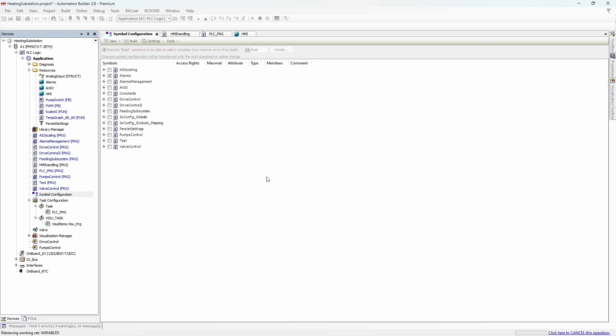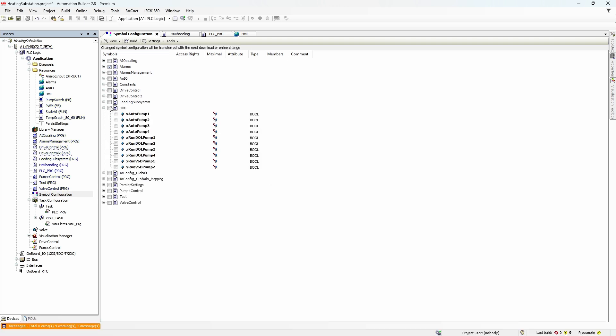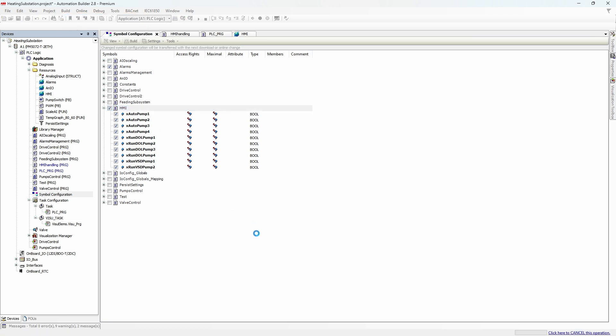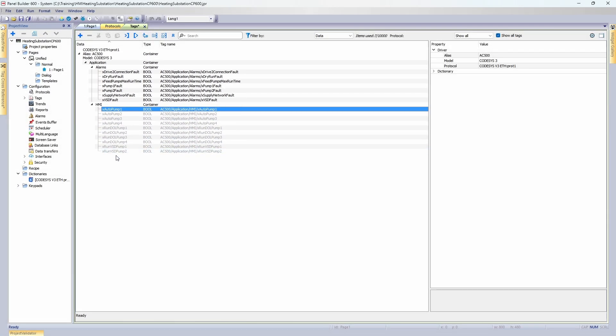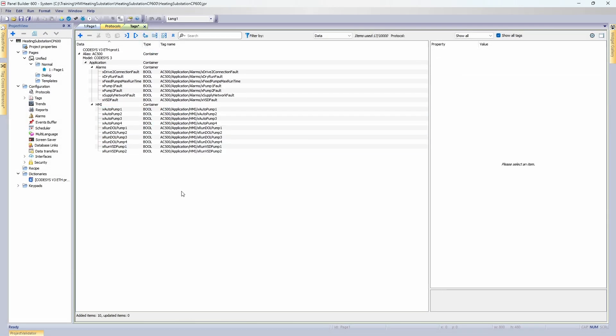When that is done, go to the Symbol Configuration window, build the project, and select everything inside the HMI group. In order to update the symbol file, go to Build, Generate Code. Now, if you switch to Panel Builder, you will see that the tags we have created are automatically populated here. You just need to click Import to add them to the project. In the next episodes, we will use these tags to build a dynamic HMI application.